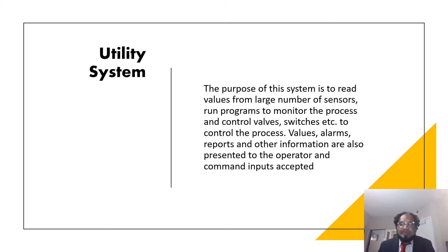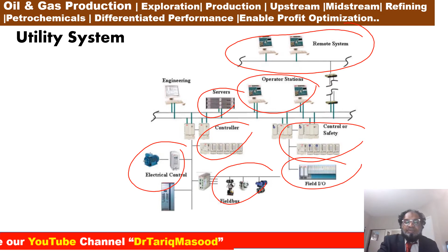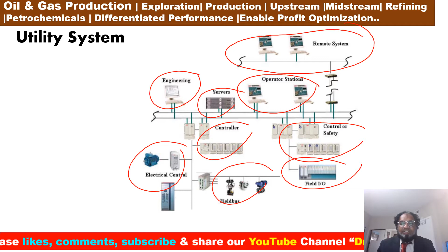Now if you can see here, the process control mechanism demonstrates that different devices are connected with a main bus bar system in a distributed system. This is my remote RTU system, remote telemetry control system, and these are my IO fields, input and output cards, this is my field bus. This is my electrical system, control devices and safety devices, and these are my servers, operator consoles, operator stations, and engineering workstation to do engineering work. These are all integrated in order to deliver the required result, which is called the process control system mechanism.